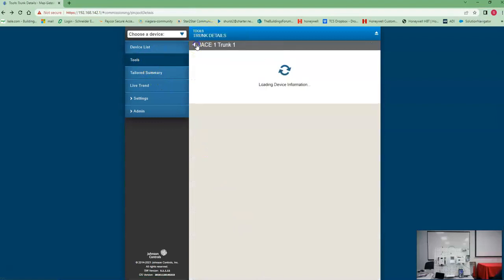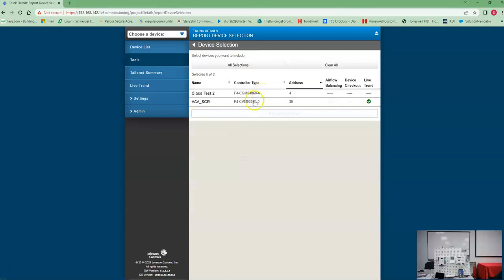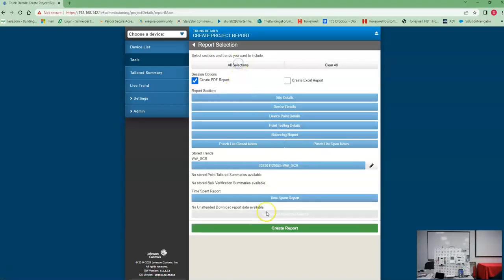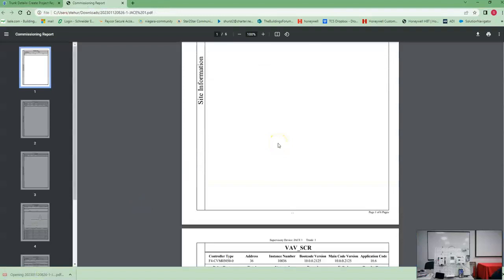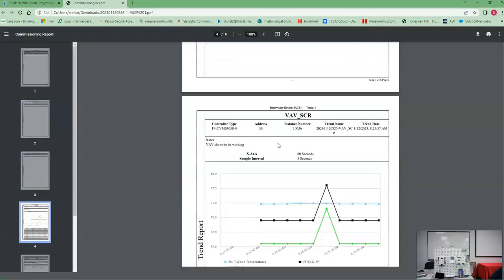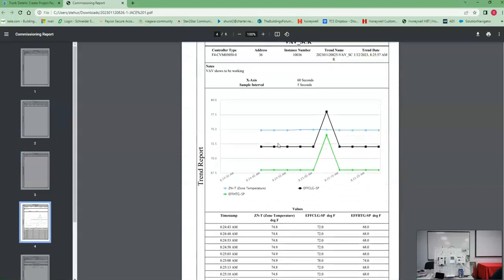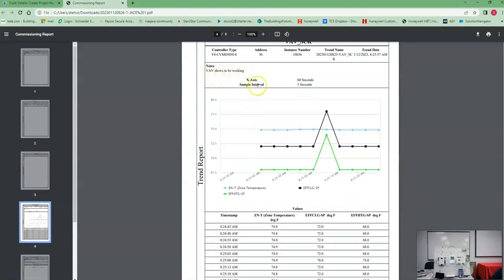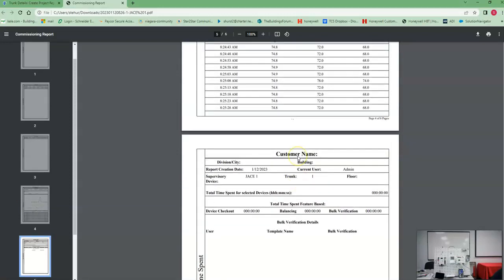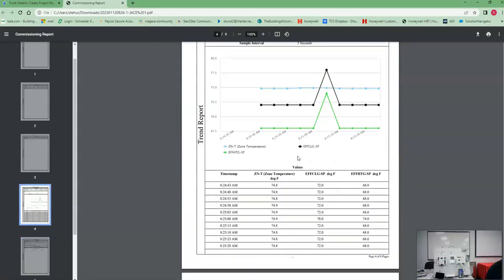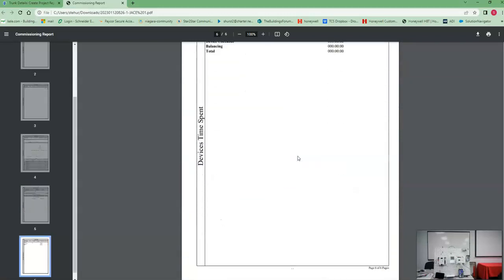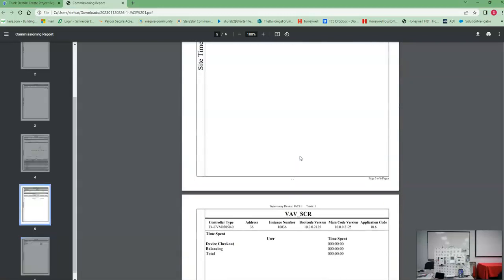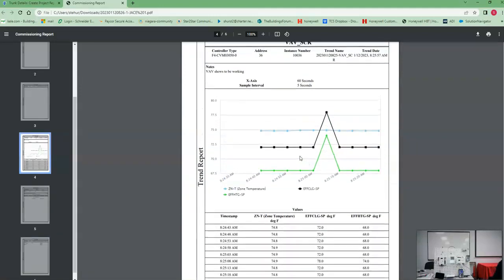So now I go back to that tools section. I want to create a report. I just want to do VAV, all sections, create a report. That's going to give me a PDF right here. Let's open up this PDF. So site information, VAVs, here's my trend, here's my notes. VAV shows to be working. Boom. So now you could spit that out to the customer after your job's done, and here's your full report on what's going on with your equipment. Obviously we could have done a device checkout, all those checkout items would be in this report.